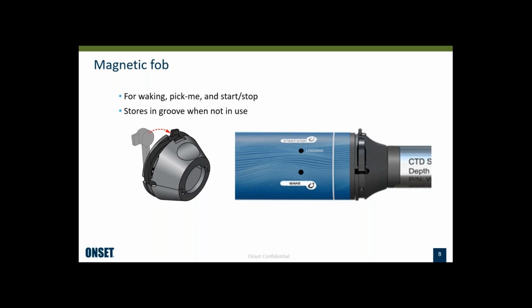You can touch the fob to the wake area, and it will raise that logger to the top of the list in the HOBO Connect software. That fob can also be used to start and stop logging if the user chooses that, either of those start and stop modes. There's a groove in the coupler that is used to store that fob when it's not being used to activate those functions.